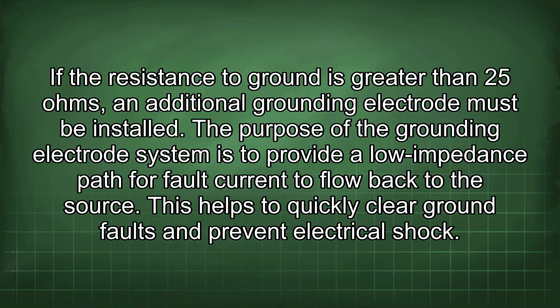If the resistance to ground is greater than 25 ohms, an additional grounding electrode must be installed. The purpose of the grounding electrode system is to provide a low impedance path for fault current to flow back to the source. This helps to quickly clear ground faults and prevent electrical shock.